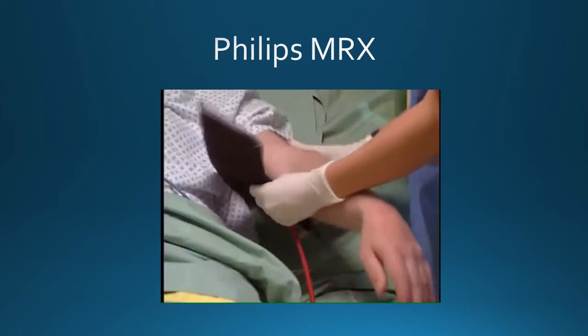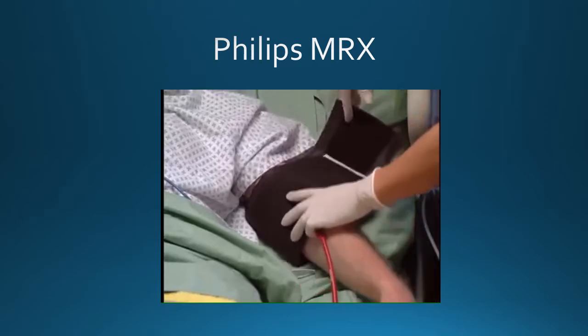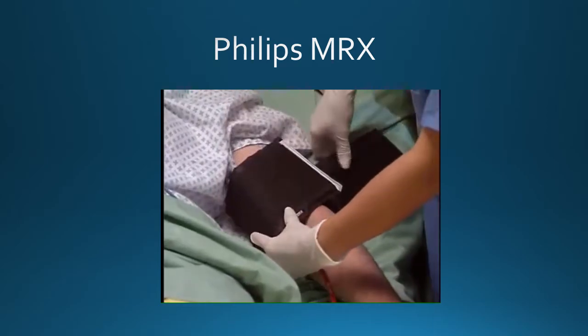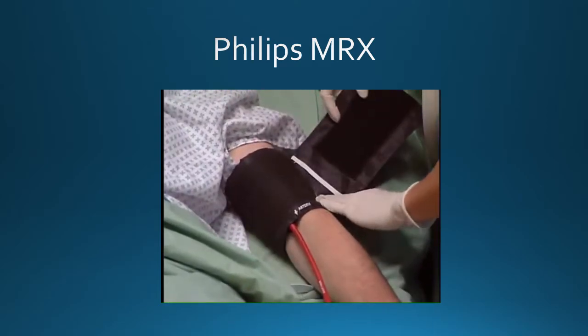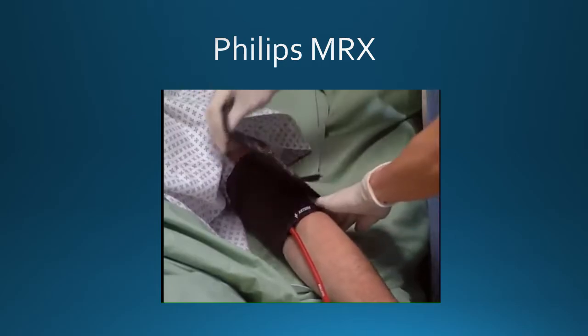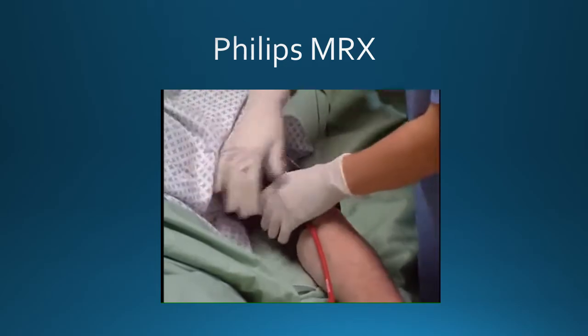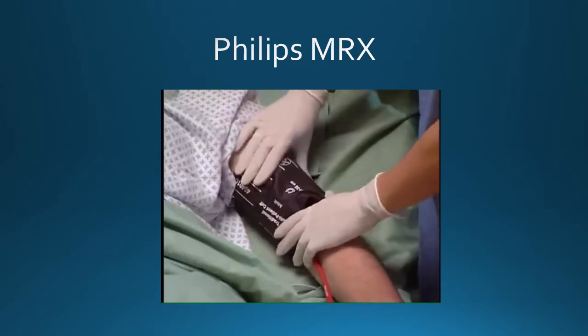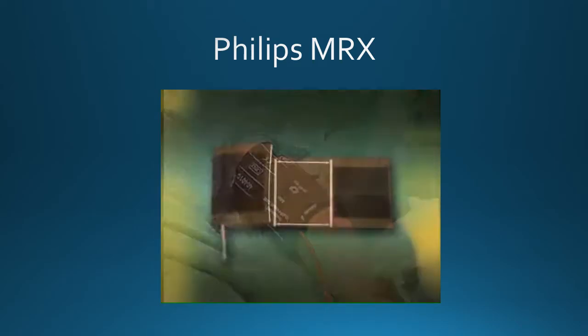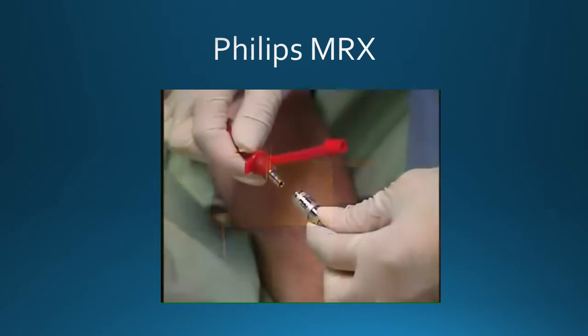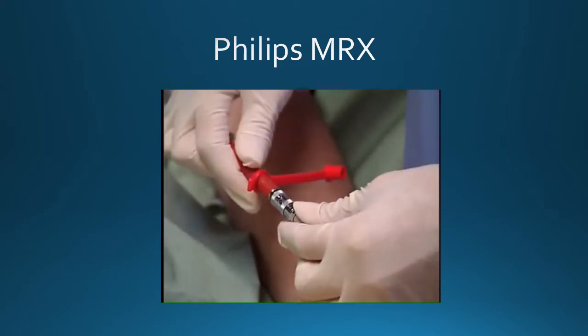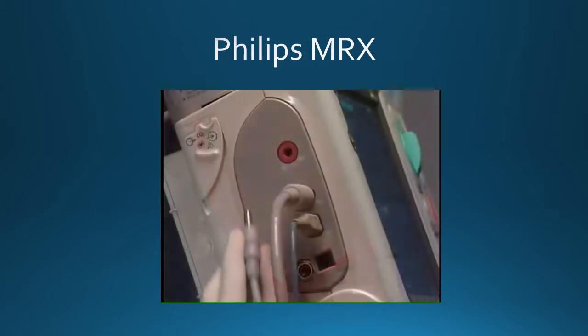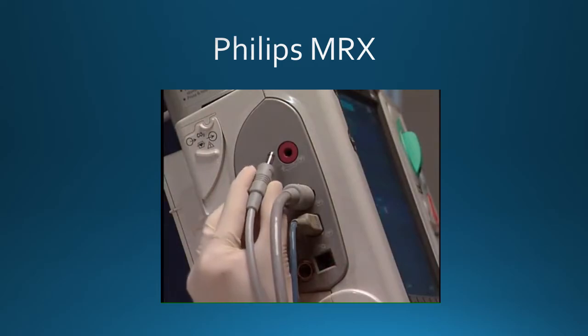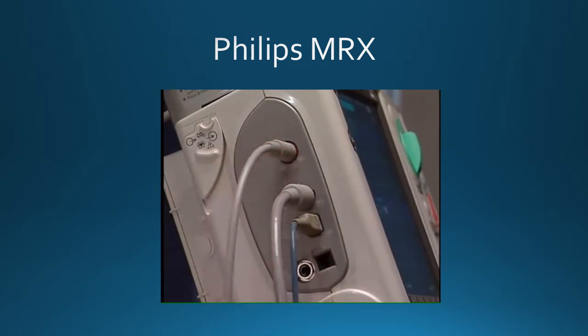The MRX can also monitor non-invasive blood pressure. The measurement can be done automatically or manually. The first step is to select the appropriate size cuff. A properly sized cuff should span approximately 2/3 of the distance between the elbow and the shoulder, and wrap around the limb meeting in the indicated area. Attach the cuff to the tubing and the tubing to the NBP port on the measurement connector module.